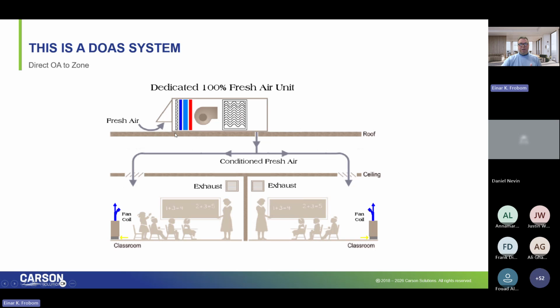Because in the applications where you've got partial outside air rooftop units or partial outside air handlers, do you really know that you're getting the right amount of outside air to these spaces? And I'd contend the answer is no. But I know for a fact with a DOAS unit, whatever CFM is coming in and then being pre-treated, I can quantify the amount of outside air. Whatever I measure, that's all outside air, and I can subsequently quantify the amount of outside air that is going to these classrooms, right? So that's a critical item, particularly post-COVID and pandemic times.